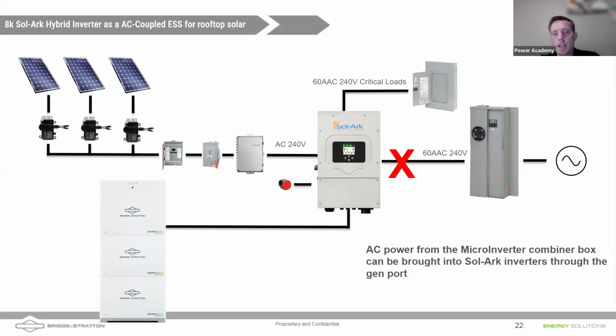But by bringing in a Sol-Ark inverter with Briggs & Stratton batteries here, we can keep that solar on by grid forming. What happens is that in a grid down event, the batteries can be drawn on by the Sol-Ark to provide backup power to the critical loads of the home. And the power the Sol-Ark is producing looks like the grid to the microinverters on the roof. That turns them back on, and they start pumping power.